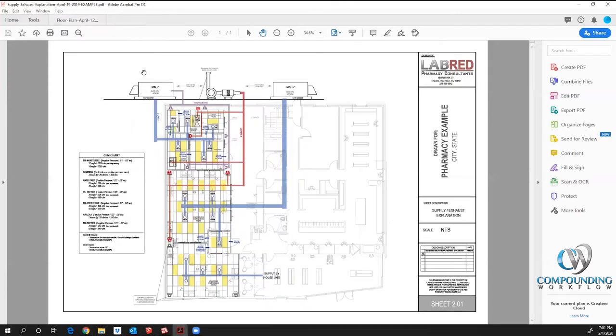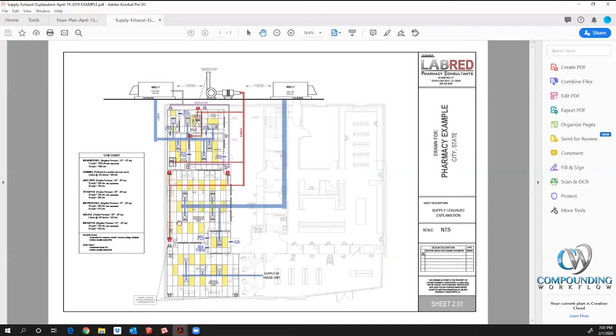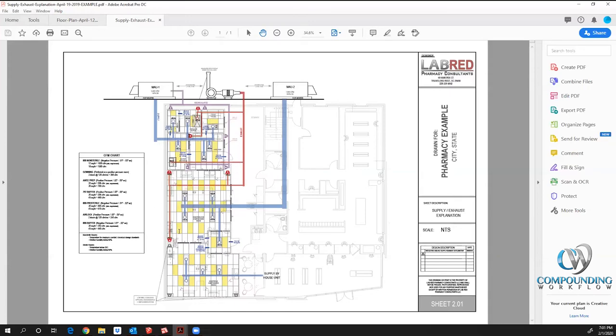The hard part is the supply exhaust program, because all of the rooms that we're now dealing with have different air change requirements, temperature, humidity requirements, positive pressure, negative pressure. USP has given us defined parameters for all the different rooms. So we designed this, and then this is the roadmap with all the pressure maps, how we're going to move the air in and out of the building, what can be recirculated and what cannot. This becomes a big piece of the pie.